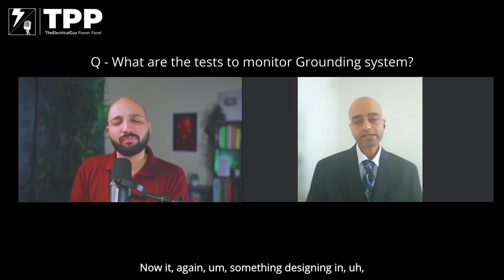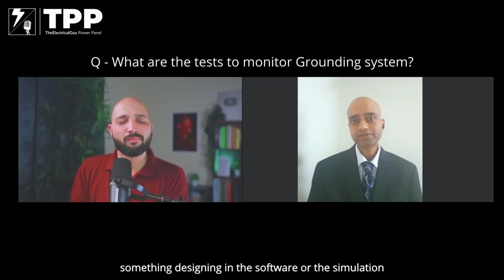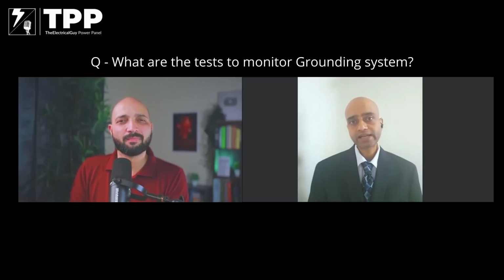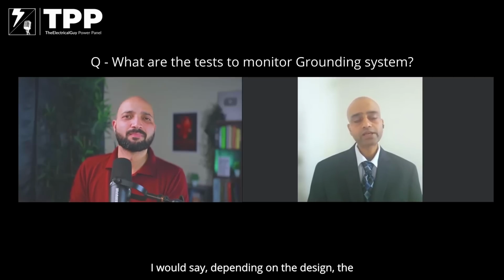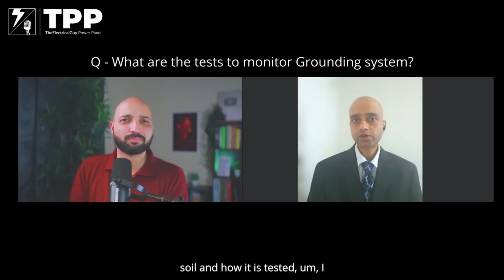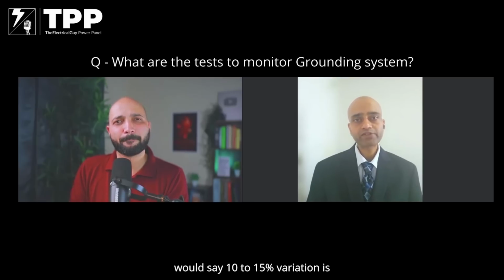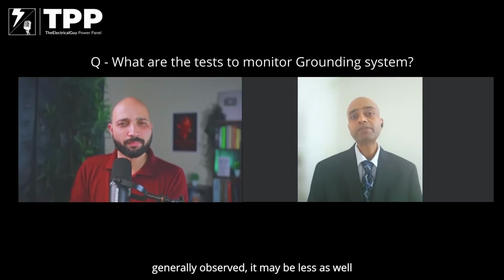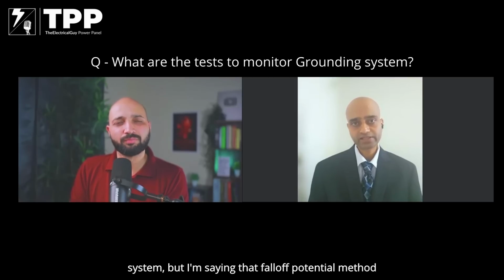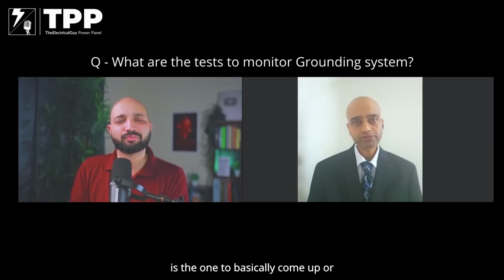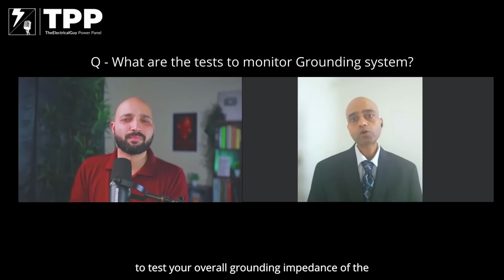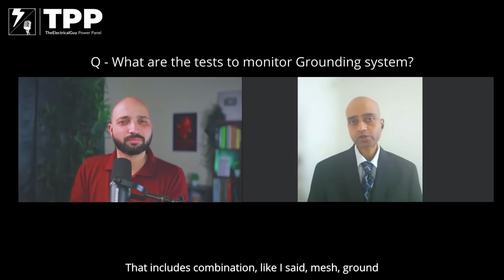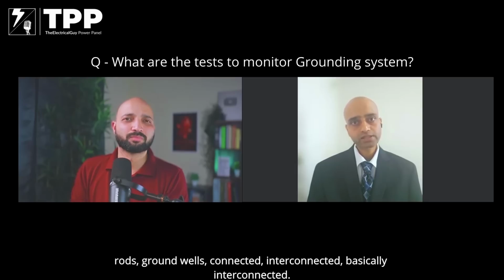Designing in software or simulation may not replicate it exactly, but the results are very close—depending on the design, the soil, and how it's tested, about 10 to 15% variation is generally observed. It may be less for a robust or well-designed system. The fall-off potential method is used to test the overall grounding impedance of the ground grid, which includes the combination of mesh, ground rods, and ground wells, all interconnected.